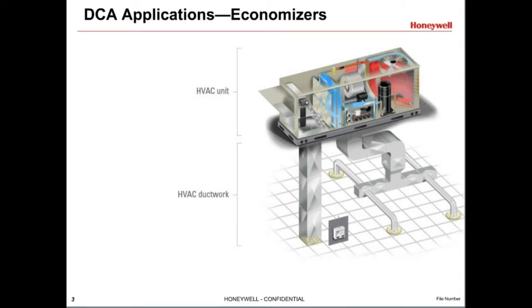Another application for DCAs is with economizer systems. Economizers use outdoor air to cool buildings when the outdoor air is cool and dry enough to use in place of or in addition to mechanical cooling. The outdoor air is mixed with return air to deliver air at a certain temperature to the space. They often use a single DCA to control both the return air and outdoor air dampers. Other units use two actuators.